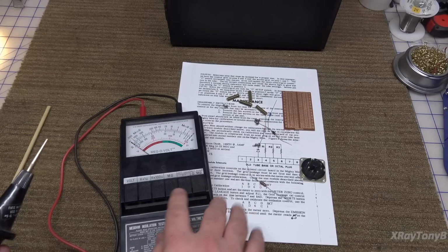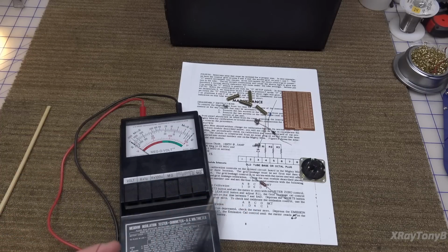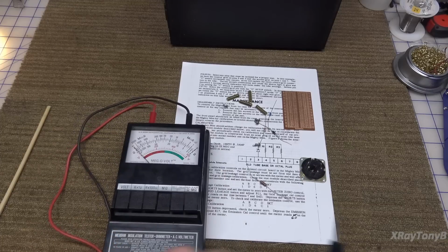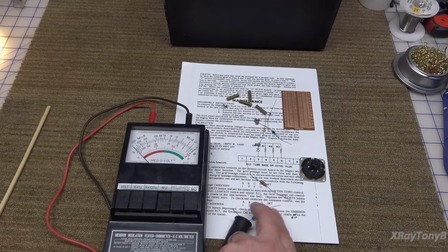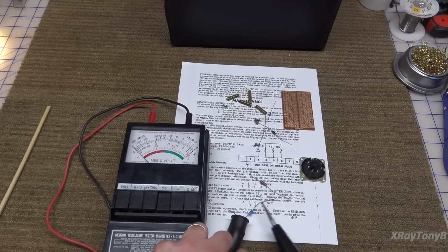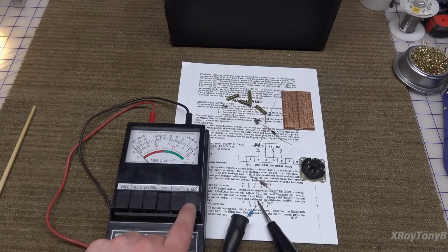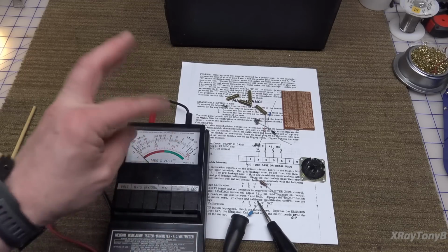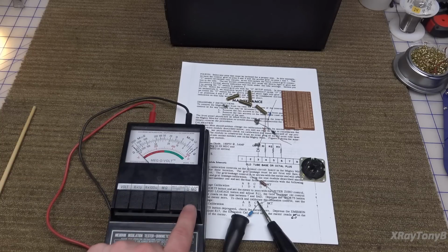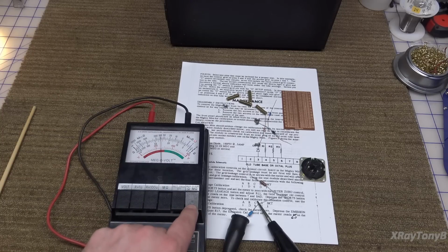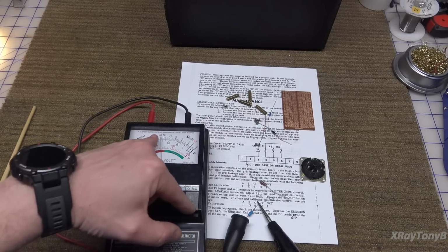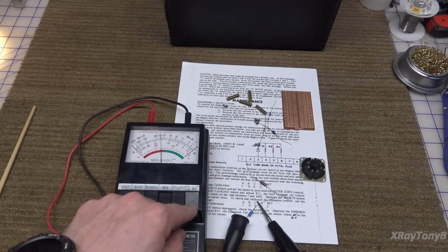And you turn it on mega ohm mode. And we'll touch it here. You don't want to put your fingers on the probes while it's running, because even though it's current limited, you get a pretty good zap. And maybe you'll hear the small whistle of the inverter making the high voltage, but here we go. And you can see right there would be 100 mega ohms, and the notch before it would be 90. That's just about right on there.